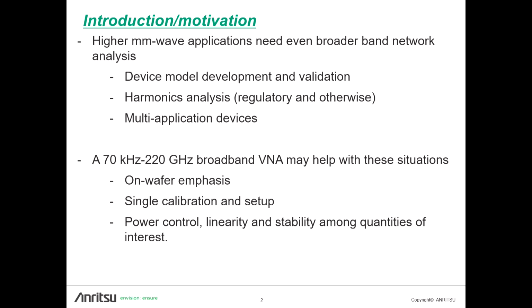As the millimeter wave measurement needs increase in network analysis, they're for both device model development validation, harmonic analysis, and then devices are used in many applications. There might be some need for a VNA that can cover a wider frequency range. And we're going to talk about one such structure that has an on-wafer emphasis with a single calibration capability to cover that frequency range of about 220 gigahertz.